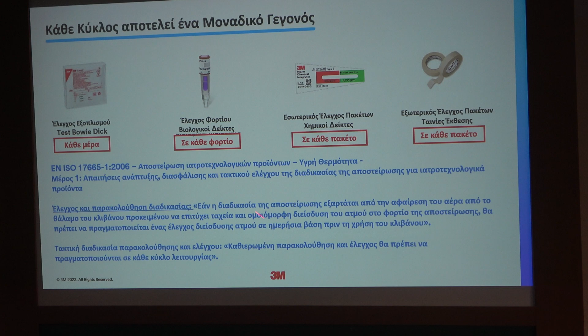One of them is, as you will see in this part, that if you are using a steam and vacuum assisted cycle, you have to do the Bowie test or steam penetration test every day. So this is something coming from the guidelines, but also the standards, because guidelines are more from the field, but when it comes to standards, they tell about the minimum requirements also for the manufacturers. And one important statement is here. It says that all cycles should be monitored because, as we mentioned, they are unique.